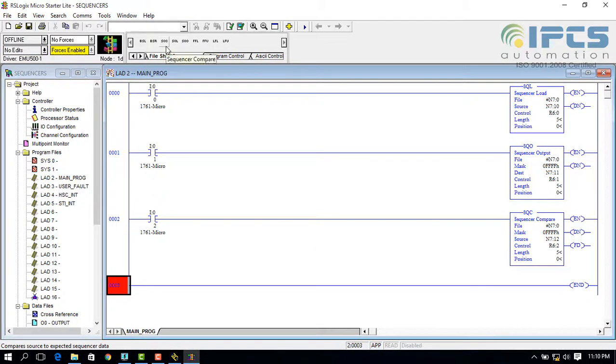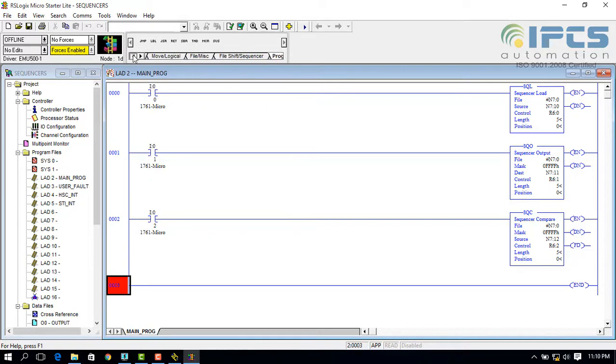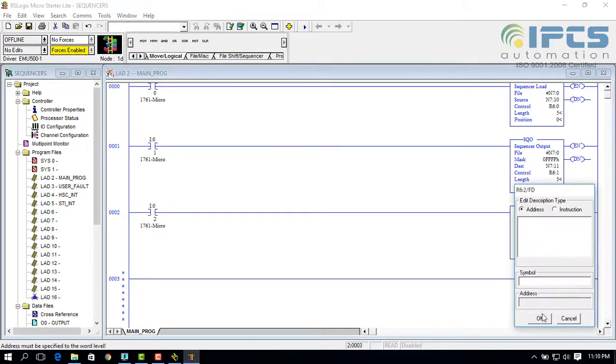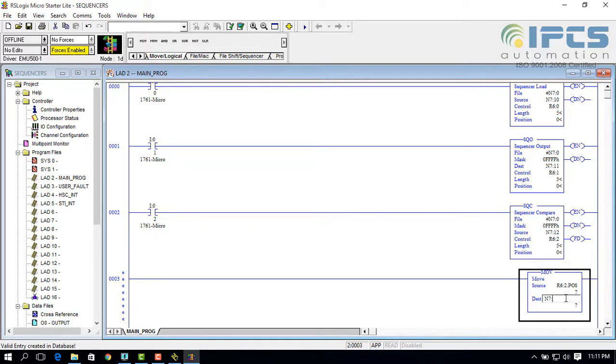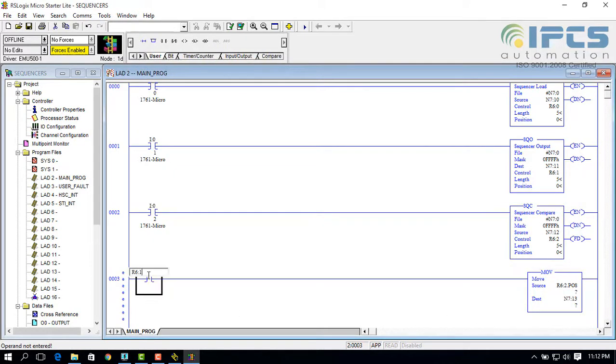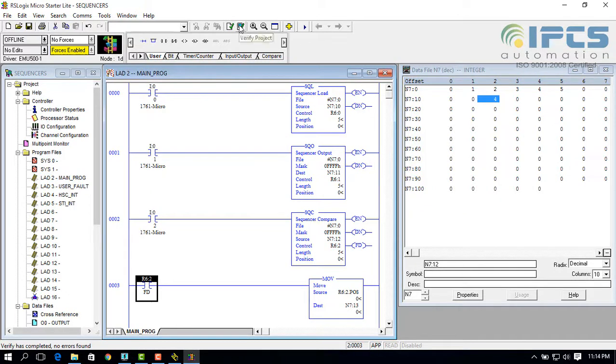And this is how the sequencers of AB work. Move instruction can be used to take out from where the value is found. The position bit of control register used in SQC is used for taking out the location. Move operation should take place while the found bit is energized, so setting it as the input coil.